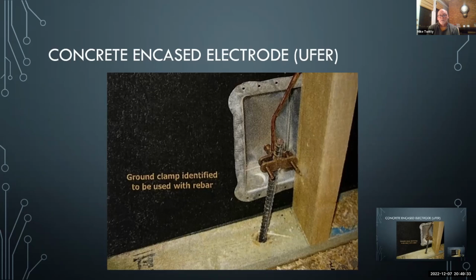Well, hey, Mike. Yes. There's a question. Is that box thing required? The box has to be accessible if it's above ground. It can be completely encased in the footing if it has a listed clamp for that. They make a clamp that can be encased in concrete and buried. In that case, of course, it's not accessible. But if it's brought up out of the footing, it has to be accessible for the clamp attachment and for inspection.